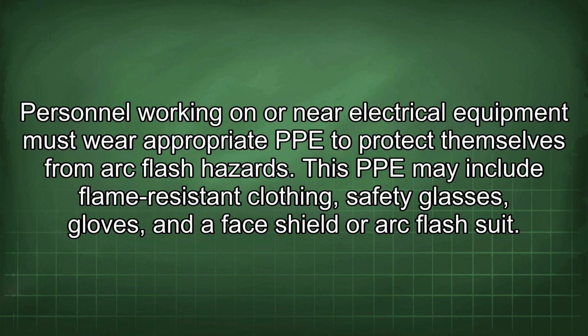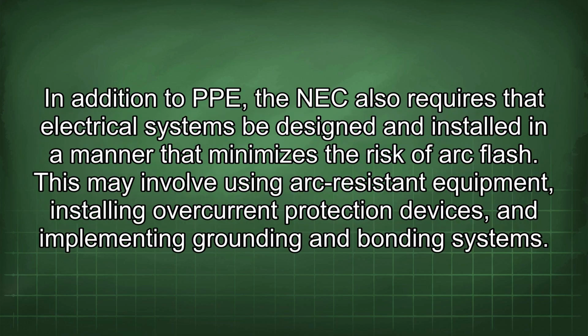This PPE may include flame-resistant clothing, safety glasses, gloves, and a face shield or arc flash suit. In addition to PPE, the NEC also requires that electrical systems be designed and installed in a manner that minimizes the risk of arc flash. This may involve using arc-resistant equipment, installing overcurrent protection devices, and implementing grounding and bonding systems.